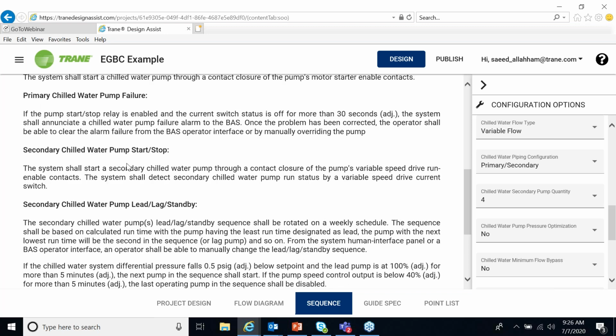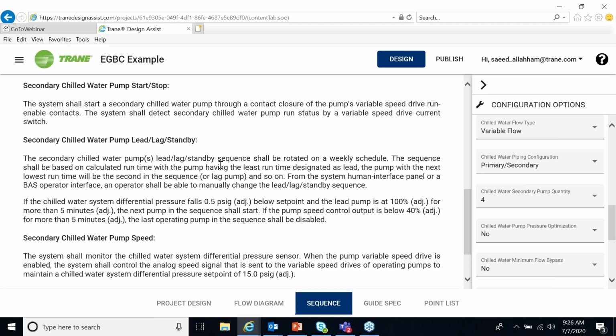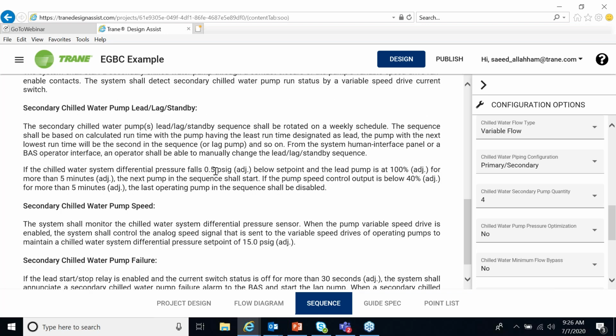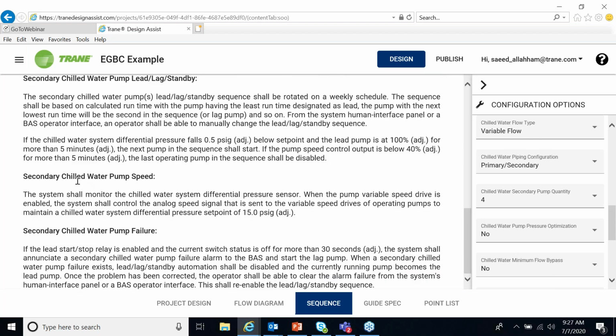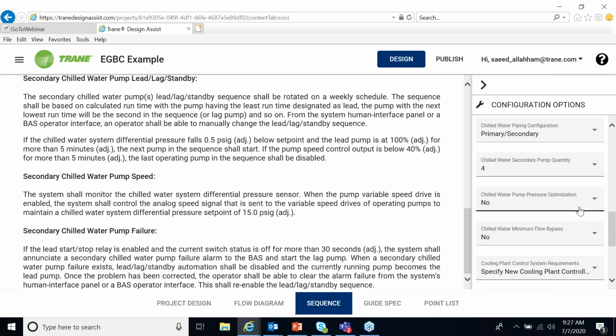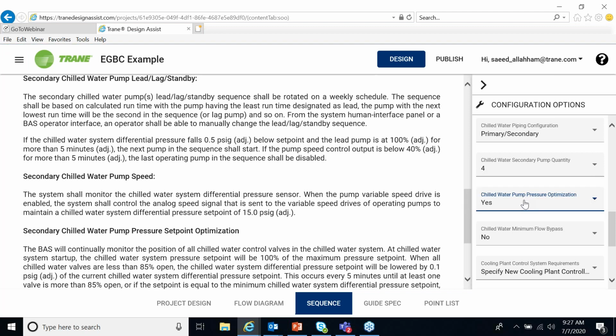For controlling the secondary pumps, it covers the lead, lag, and standby, the control philosophy, and how it starts the second pump or stops the pump. It will describe here the control of the secondary pump variable speed drive, which is based on maintaining a pressure set point of 15 psi, for example, and this is adjustable. So all of that is generated automatically based on the configuration. For example, here we talked about chilled water pump pressure optimization. I don't know what that is, so I will select, for example, chilled water pump pressure optimization.